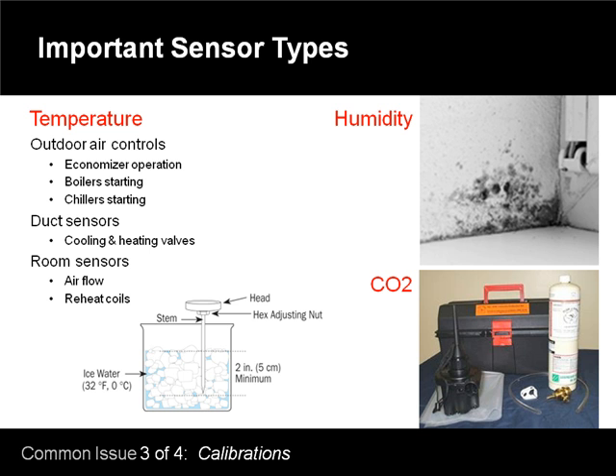So anytime you have a temperature sensor controlling a piece of equipment, it's very important that you turn that equipment on or off correctly, to save money and to economize on what utility costs are going to be. Turning a chiller on when it thinks it's 50 outside and it's actually 45 outside is not a good thing. So the calibration of these controls is what we want to address here.